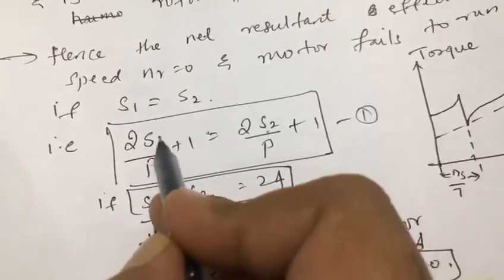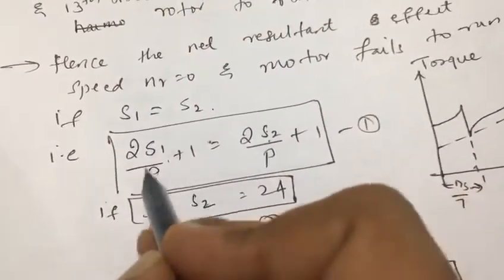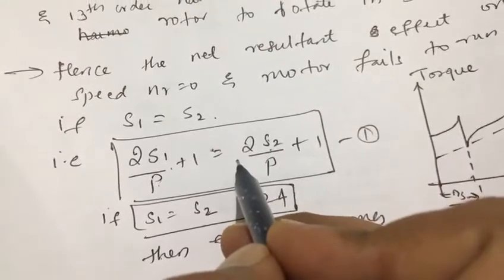If we solve this by taking p as 4 and s1 and s2 as 24, then for the 11th and 13th order harmonics, one will be opposite, another will be in the same direction. So the net effect will be zero.